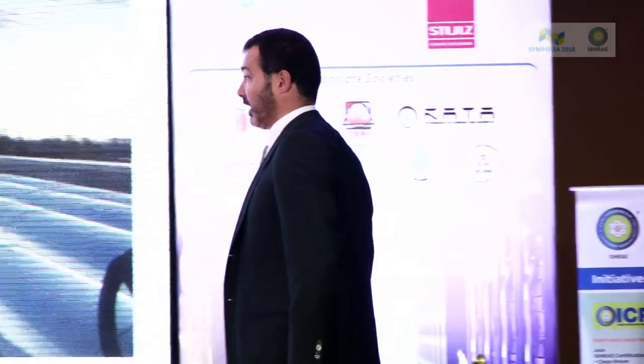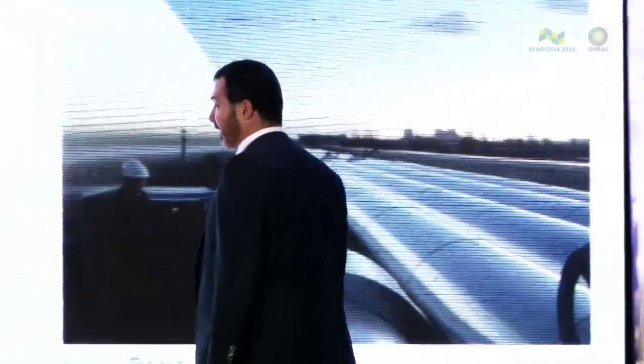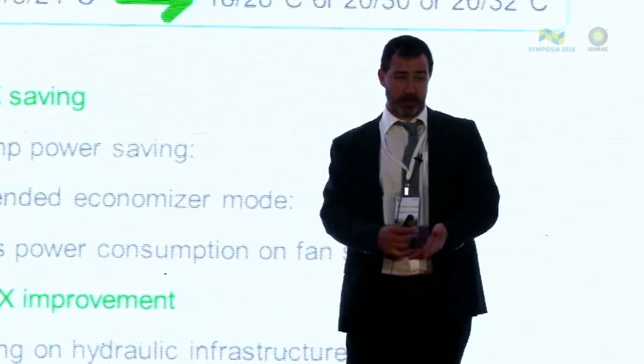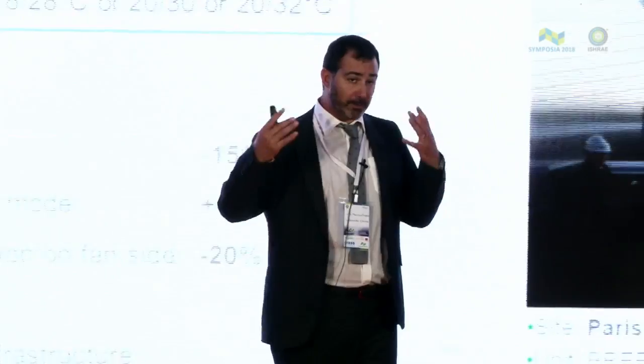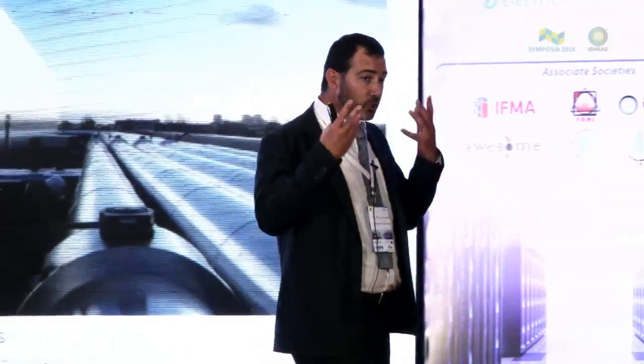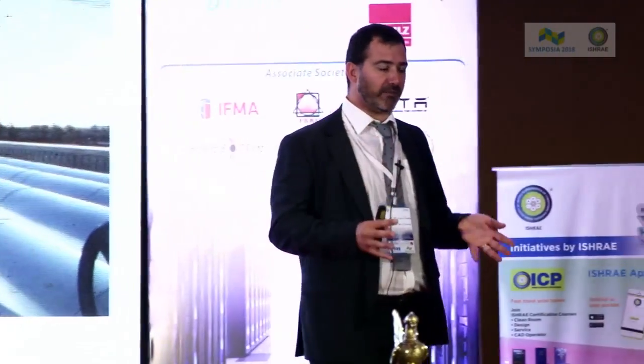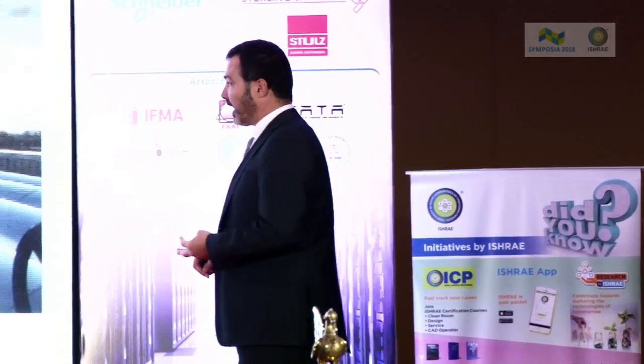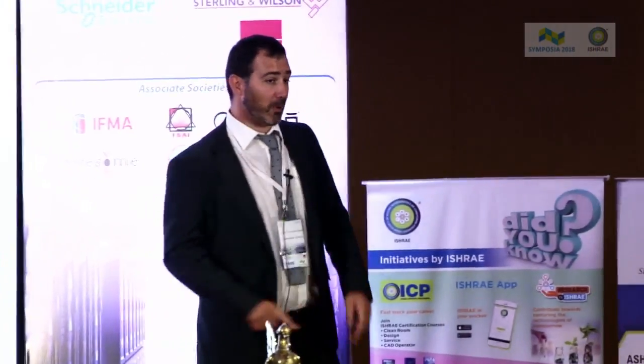So definitely on the CapEx investment, the pumps are smaller. The electrical infrastructure for the pumps is smaller. The piping is smaller. So the pressure drop is smaller. So everything is definitely more interesting from the CapEx perspective, but smaller pumps means less power consumption. Less water flow means less pressure drop. So again, less power consumption on the water side.